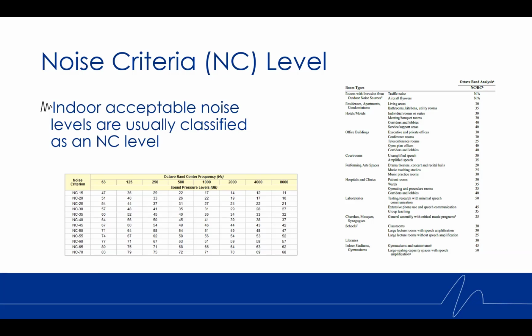And what an NC 30 or an NC 40 or 50 means, it basically dictates the highest amount of sound pressure at each frequency that is deemed acceptable. So in the chart at the bottom here, you can see the maximum sound pressure levels at each frequency in order for the room to meet that noise criteria level. So when you're looking at the actual sound pressure levels in a space, we want to make sure that the measured levels are the same or lower than the target NC level for that room.